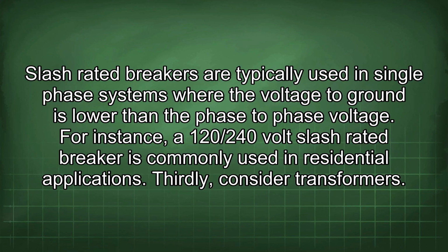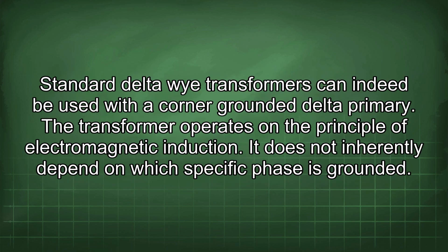Thirdly, consider transformers. Standard delta-Y transformers can indeed be used with a corner-grounded delta primary. The transformer operates on the principle of electromagnetic induction. It does not inherently depend on which specific phase is grounded.